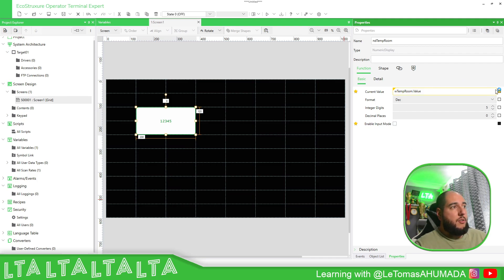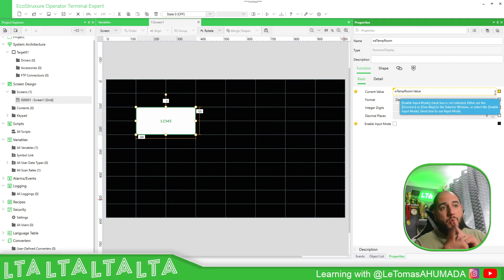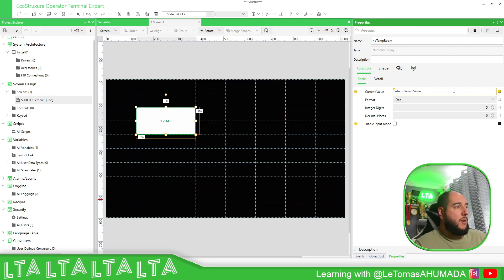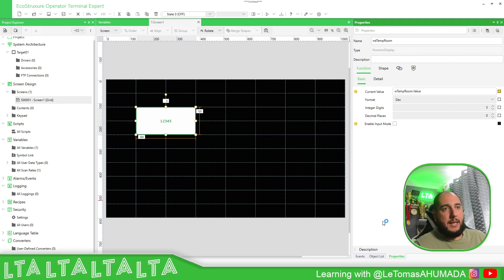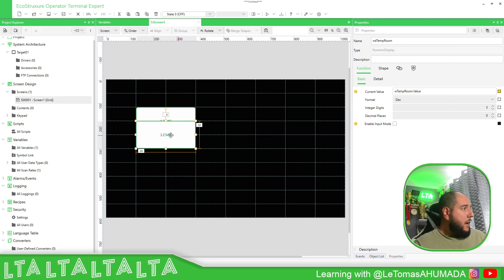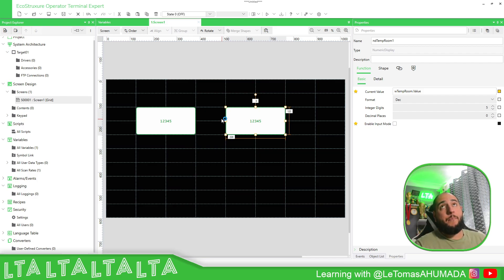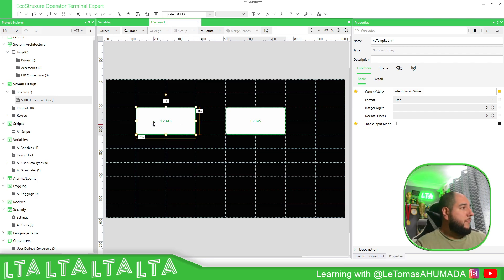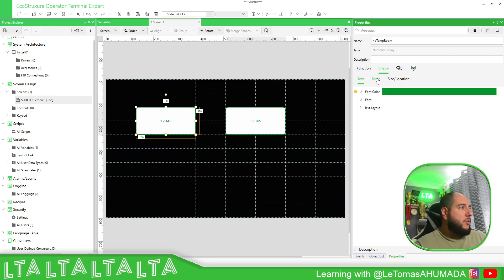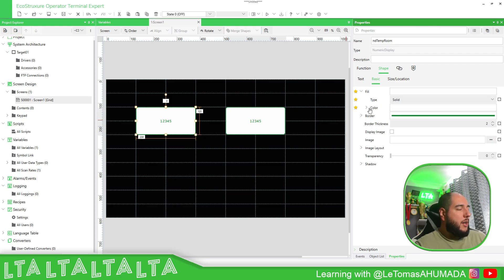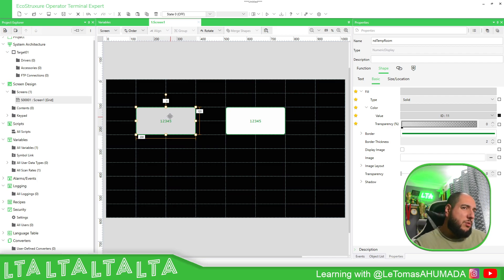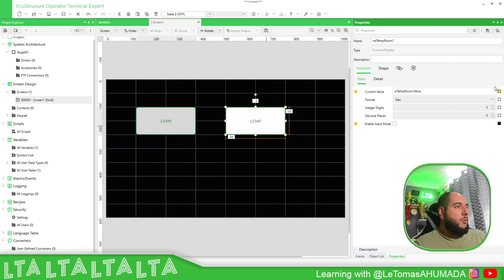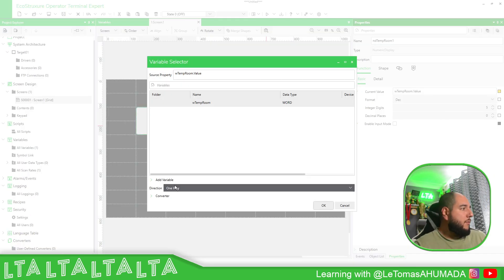If you use two-way it means you need to enable the input. If you don't, you should see this in yellow because the object is configured as two-way but you haven't enabled writing. So in this case I go back and use one-way — you can see there's no yellow indication. For this particular case, since it's going to be read-only, what I usually do is change the font fill to something like a little bit of gray, giving the visual meaning that you cannot write into this one even if you touch it.